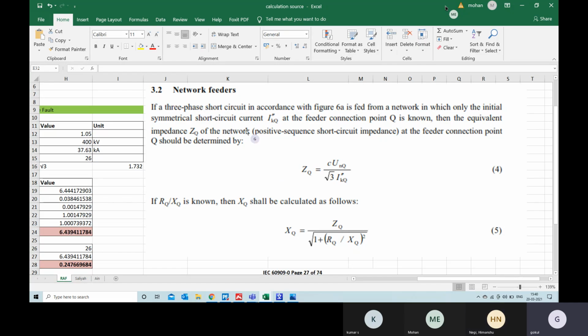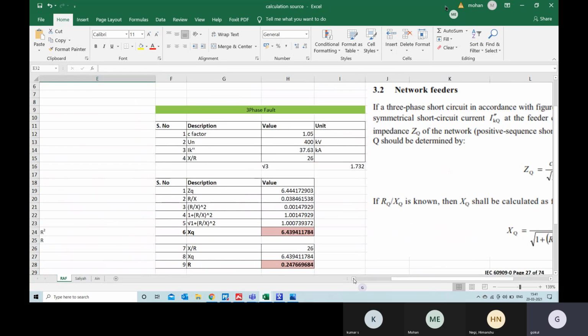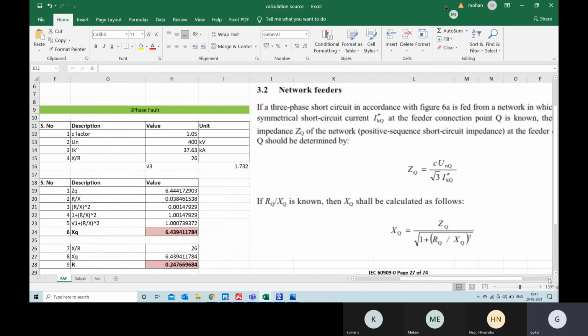IEC 60909 clearly says that this formula or calculation is only used to find the positive sequence, not for zero sequence. So we should not be misled that we can use it for both positive and zero sequence. You get a good understanding of why we use this only for three phase, because there is no ground fault. So we can first do the three phase fault current, and then go for the single line to ground fault.